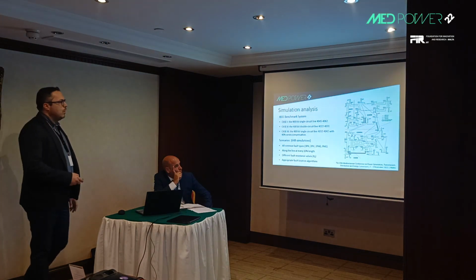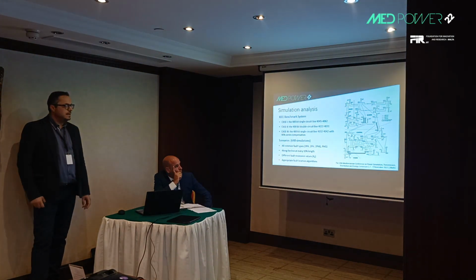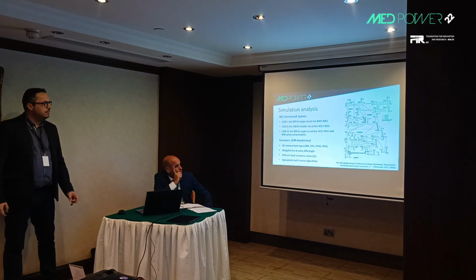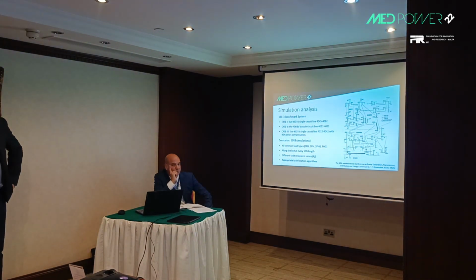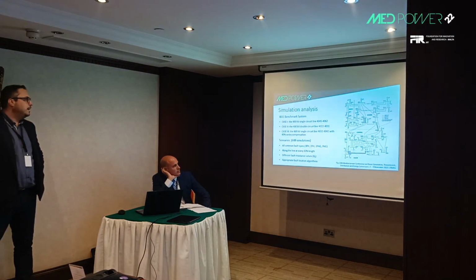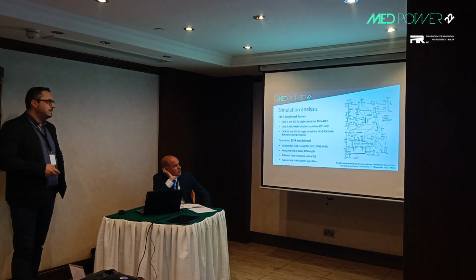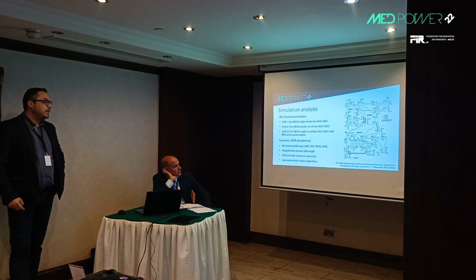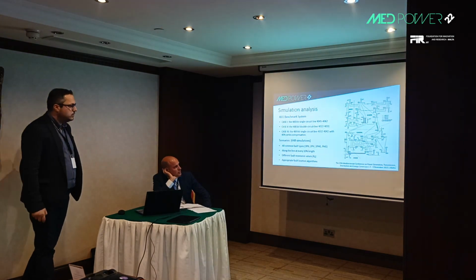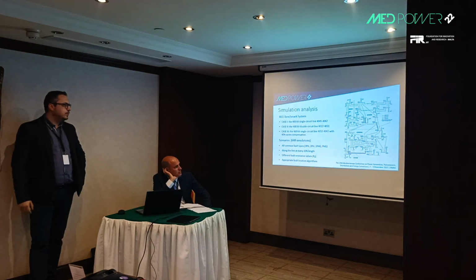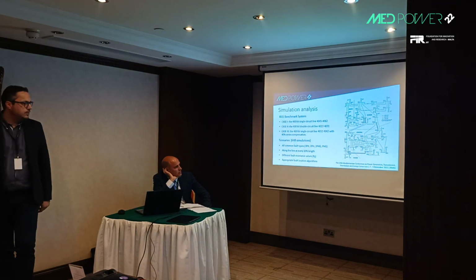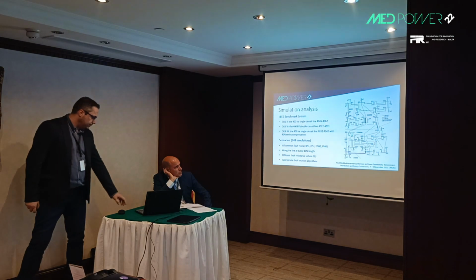We applied all common fault types, namely the three-phase, the double phase to ground, the double phase, and the phase to ground fault on each of those lines, and along these lines at every 10% length. And for each of those short circuit scenarios, we assumed different fault resistance values. In total, 648 simulations were conducted.